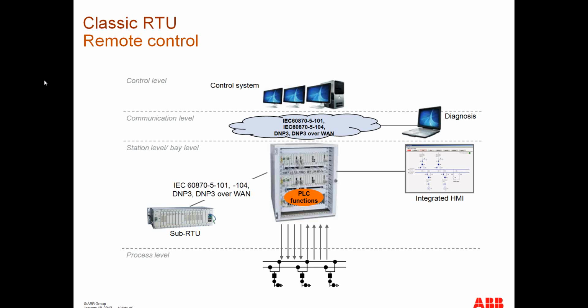And of course, in the RTU we have these PLC functions integrated, and normally the human-machine interface to really act at the RTU, and then the RTU sends information to the control level via different protocols. You can see here 101, 104, of course DNP3 or DNP3 over WAN, which means Ethernet connections or serial connections, depending on the application level.